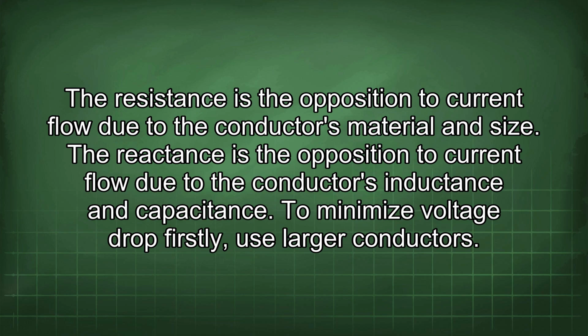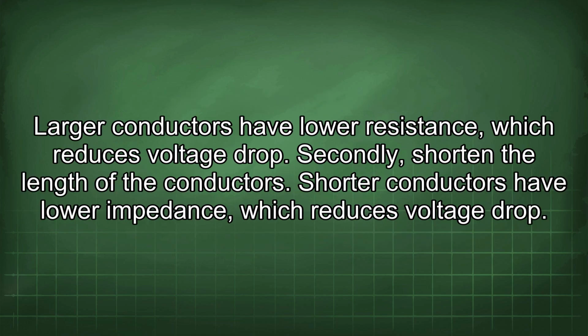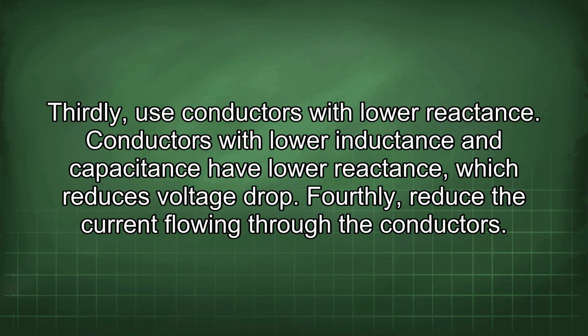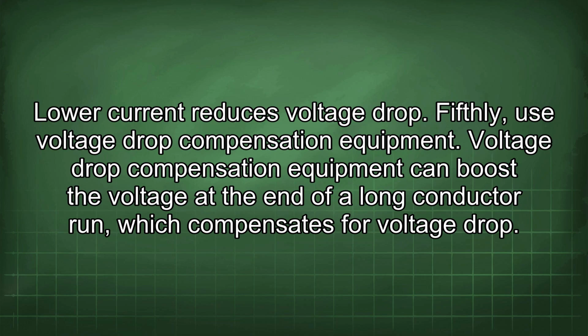To minimize voltage drop, firstly, use larger conductors. Larger conductors have lower resistance, which reduces voltage drop. Secondly, shorten the length of the conductors. Shorter conductors have lower impedance, which reduces voltage drop. Thirdly, use conductors with lower reactance. Conductors with lower inductance and capacitance have lower reactance, which reduces voltage drop. Fourthly, reduce the current flowing through the conductors. Lower current reduces voltage drop. Fifthly, use voltage drop compensation equipment. Voltage drop compensation equipment can boost the voltage at the end of a long conductor run, which compensates for voltage drop.